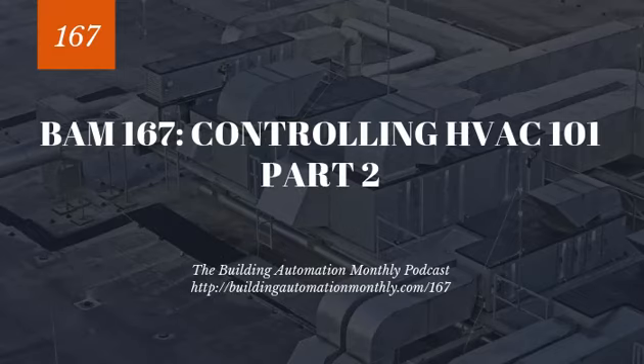100% outdoor air unit. Now, I know some of you who are in Florida or in Louisiana are saying, Phil, this wouldn't work there. I agree to a point. You're absolutely right. Typically, folks will have units before the 100% outdoor air units that exist solely to remove that humidity. But in most places, 100% outdoor air units can actually remove a lot of humidity using coils and things like approaching saturation.